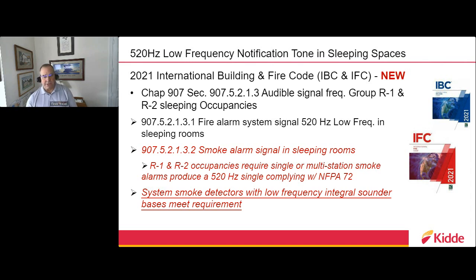So to meet the code requirement today, you would actually have to install a fire alarm system smoke detector in the commercial sleeping occupancy type application. That would have to be that 520 hertz low frequency base that we just previously touched on in the previous slide, and you would have to have that system smoke detector installed into the base. And now with the programming sequence that you can do with a Kidde FX panel, you can make that detector operate for what we would classify as a standalone smoke alarm in-room operation. So when the detector goes off, it only activates that sounder base. But you can also program the system to operate as a general alarm notification horn, so that if someone pulled a pull station, that same sounder base can be used for notification within the actual space itself.